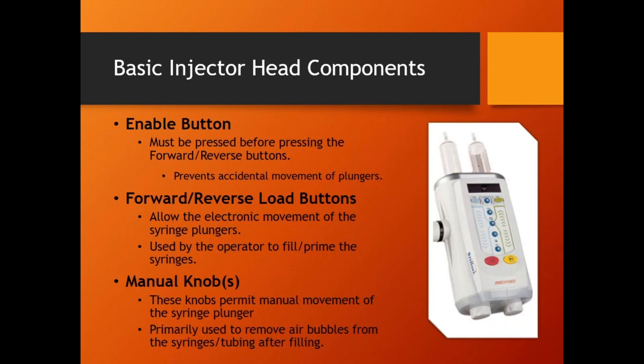They love it. But one of the things the injector head does not have is manual knobs, and it does not have a forward reverse load button. There is no way. It is not possible. If I want to just move that piston forward or reverse a little bit, too bad. Shut me down, start me over. That's the only way to do it. That takes about 5 minutes. So there's no even software way on the screen.